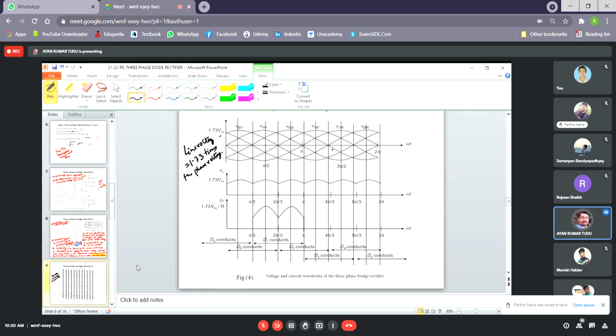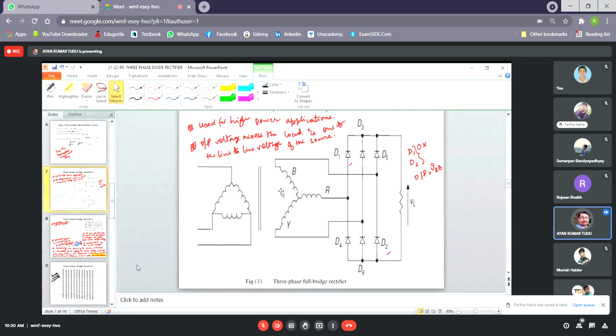Please remember that in this particular circuit, it is permissible to use any combination of star or delta connected primary and secondary windings because the currents associated with the secondary windings are symmetrical.